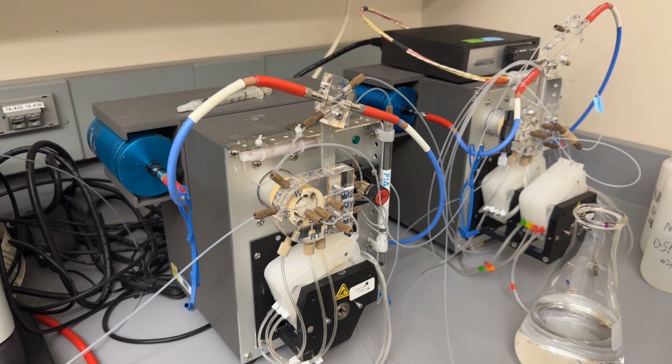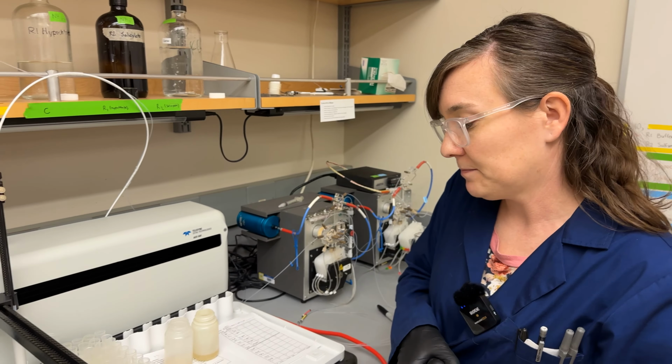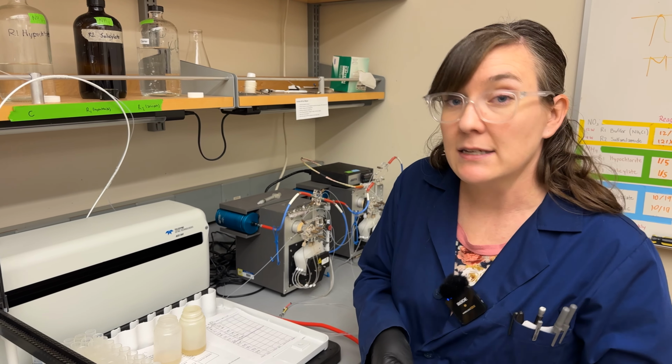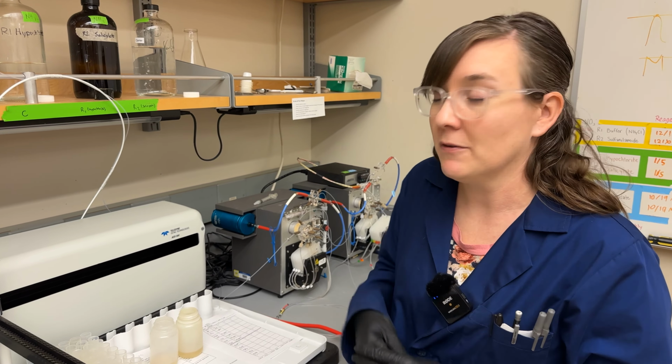So flow injection analysis, basically it's an automated spectrophotometer. It pulls in the reagents. The injection system here in the middle adds the sample to the reagents, and then it measures on the spectrophotometer.